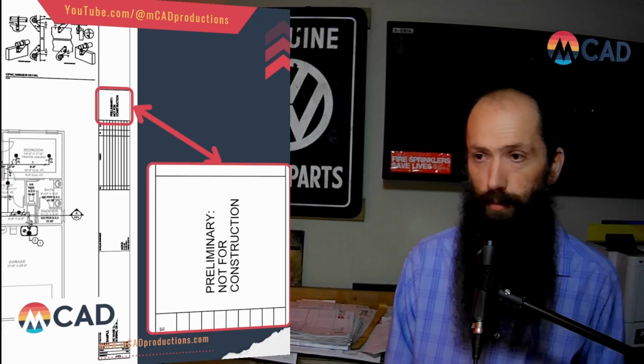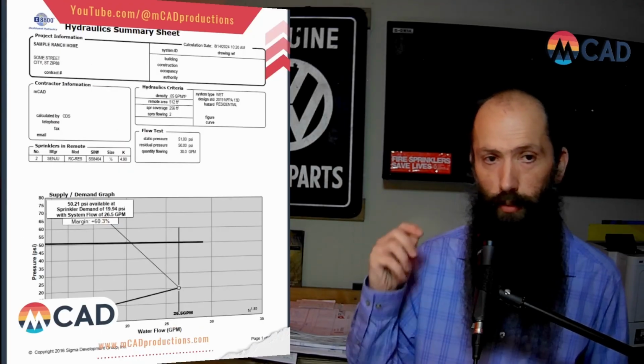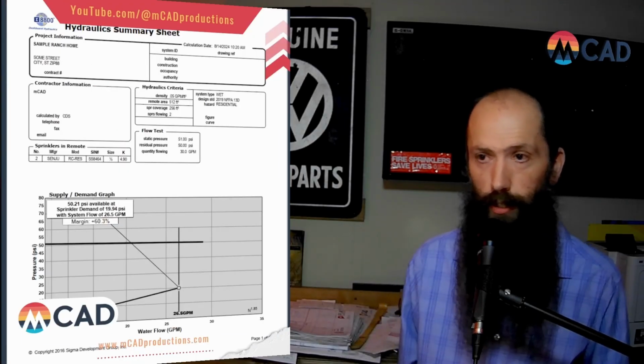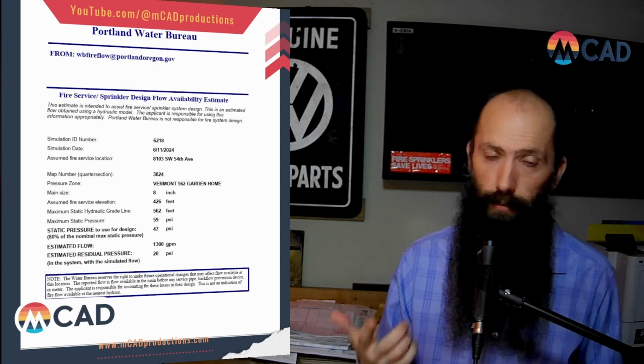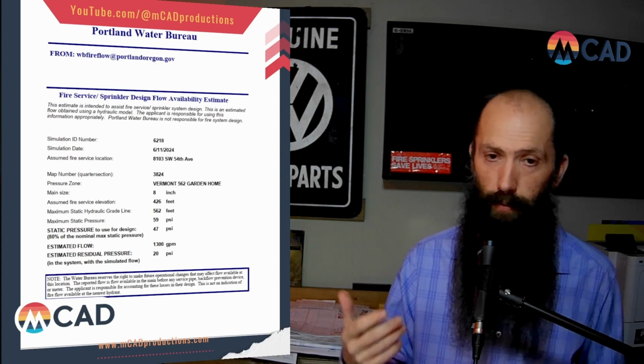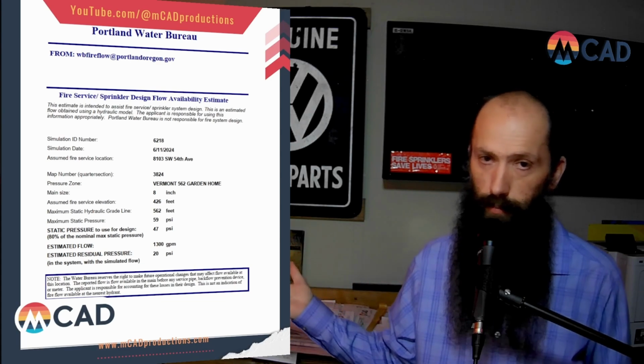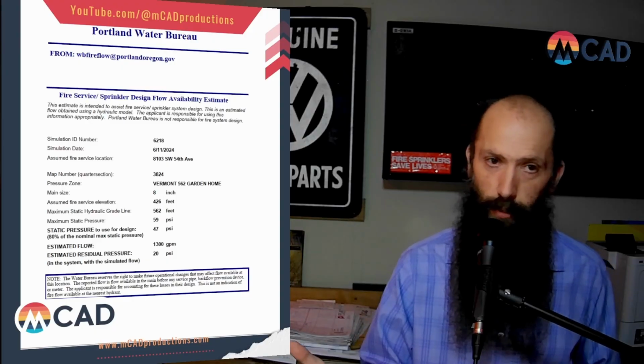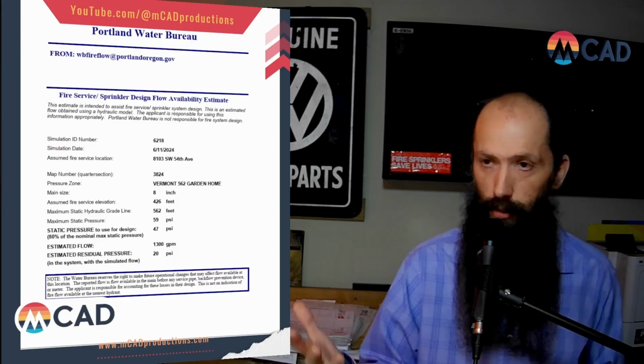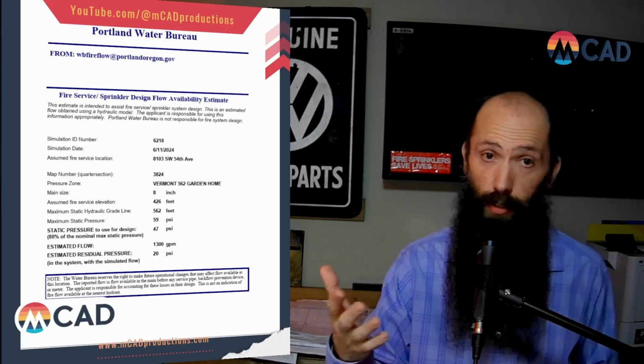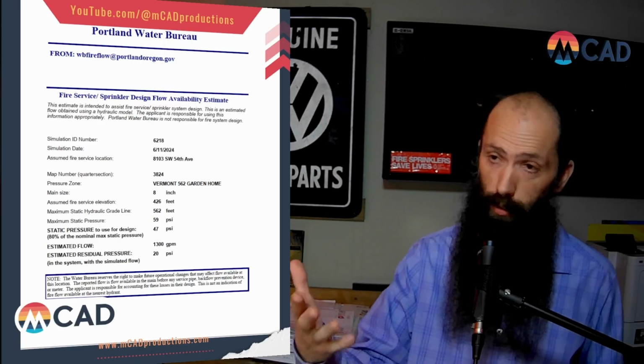And that's it. So we get our drawing, we get our hydraulic calculations. If there was a hydrant flow test report done by the local water jurisdiction, it's not uncommon, then you usually have to include that report with your submittal. We ended up doing a tank and pump, but if I was doing a drawing in the city of Portland on the Portland Water Bureau's water supply, I would include this form with that.